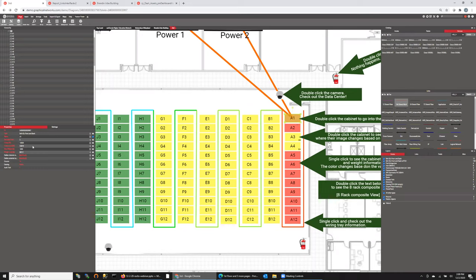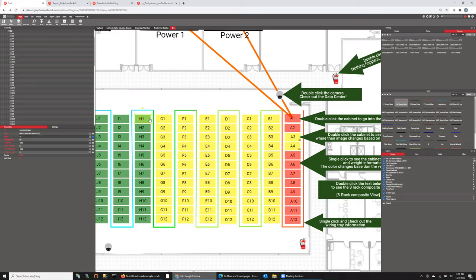If I click on a cabinet on the left-hand side, you'll see information about it — like it's got 10,000 watts of power, and it's consuming more than 10,000 watts of power based on the equipment inside. The max weight is 1,000 pounds and I've got 897.2 pounds of weight inside the cabinet. This is a 42U rack with one rack unit available, which is why it's red. Green is basically an empty or near-empty cabinet. Green-yellow usually means it's around the 60–80% utilization mark, and greater than 80–90% gets you into the red range. You can change those threshold values.